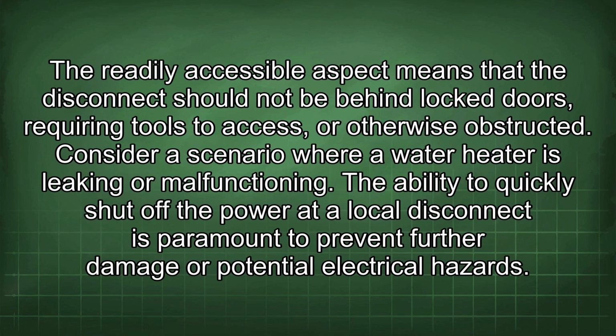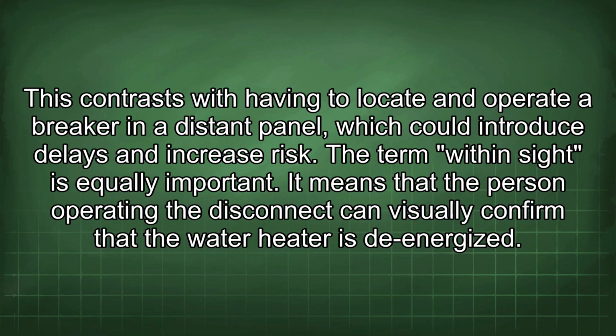The readily accessible aspect means that the disconnect should not be behind locked doors requiring tools to access, or otherwise obstructed. Consider a scenario where a water heater is leaking or malfunctioning. The ability to quickly shut off the power at a local disconnect is paramount to prevent further damage or potential electrical hazards. This contrasts with having to locate and operate a breaker in a distant panel, which could introduce delays and increase risk. The term "within sight" is equally important.